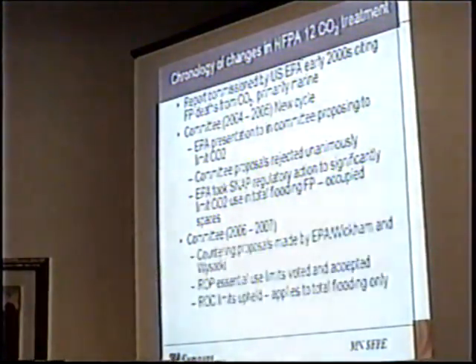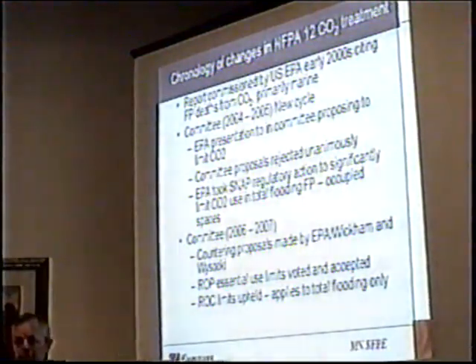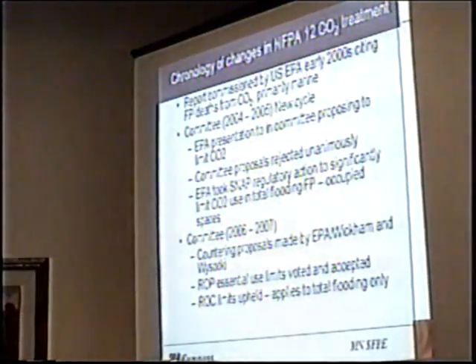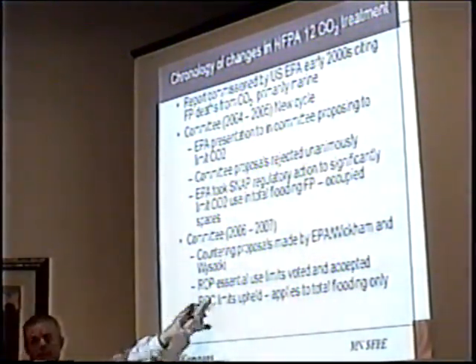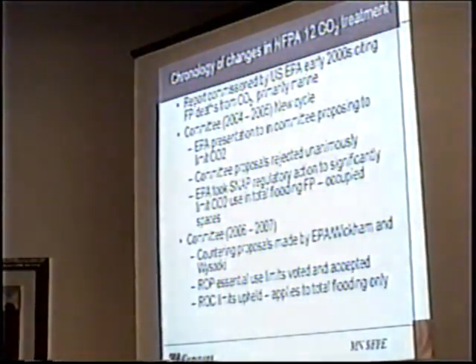Committee work in 2006, 2007. Some countering proposals were made by EPA and a consultant, Bob Wickham, and Tom Wysocki, who's chairman of NFPA 12, before it was switched around. Basically, the committee put essential use limits that were voted on and accepted at that point in time. Those limits were upheld in the ROC. It applies to total flooding only, not local application. By the way, 3M supported the limits on total flooding, in that we actually pulled all of our total flooding systems out because of our concern for safety. We still have local application, but we had long ago pulled out our total flooding.